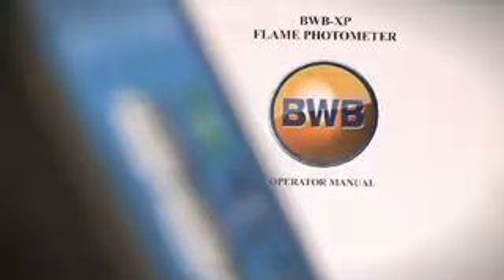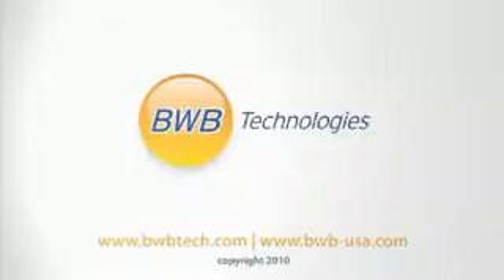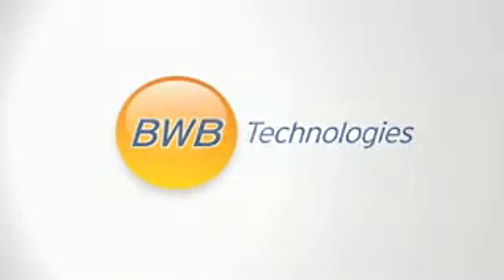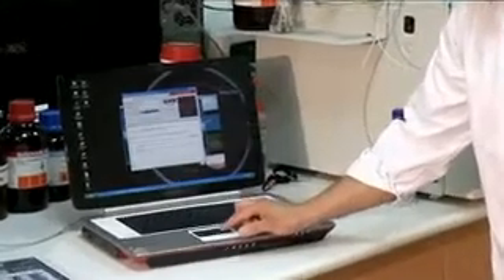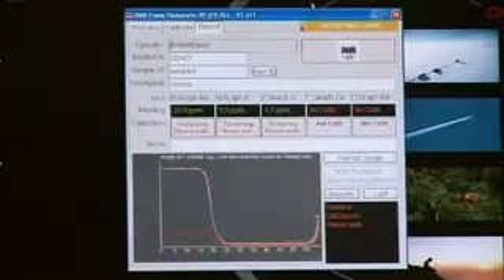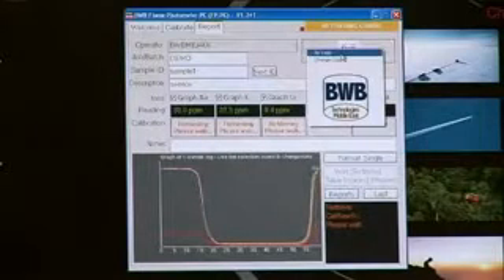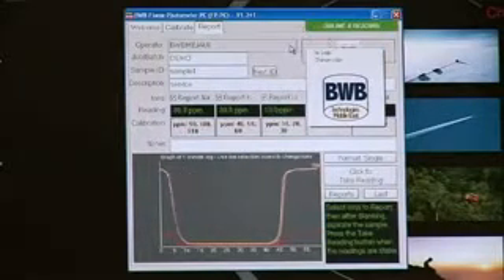Aspirate standard 2 and watch on the FP PC. Repeat for standard 3 by entering 110 for sodium, 60 for potassium and 30 for lithium. Aspirate standard 3 and watch on the FP PC. Remember to tick the retrieve calibration boxes for each ion calibrated. The multi-mode calibrations offered by the Bwb Xp has allowed us to cut our calibration time by 2/3. The more ions and points desired, the more time you will save.